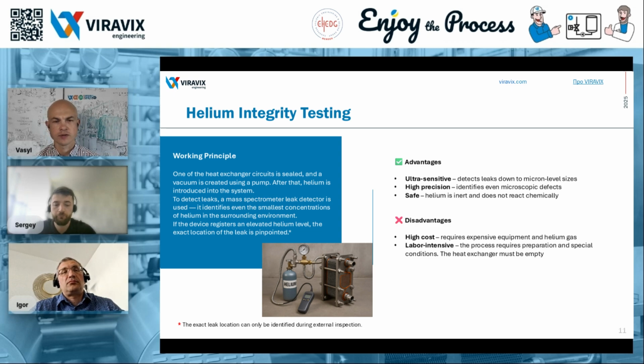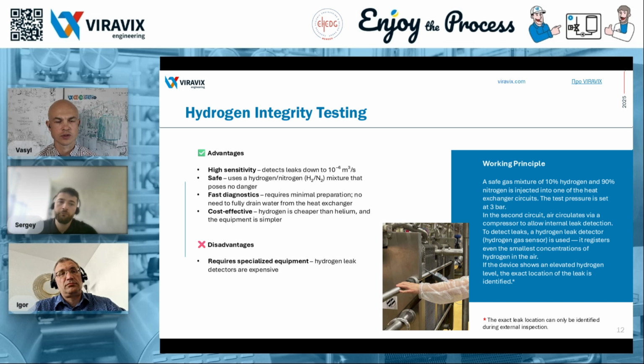And I think we can now move on to the hydrogen test, which, as I understand it, is quite similar in principle to the helium test. The main difference, Sergey, is in the type of gas mixture used for testing, right? Yes, mostly the gas mixture. And of course, the leak detector will be different. It's specifically designed to detect hydrogen. Please tell us about this test.